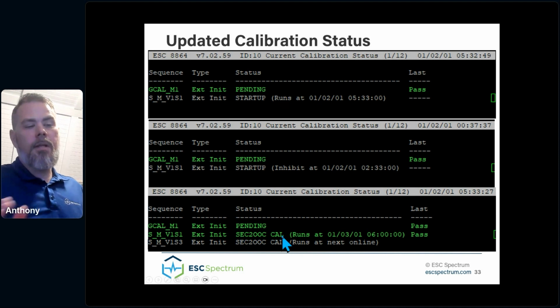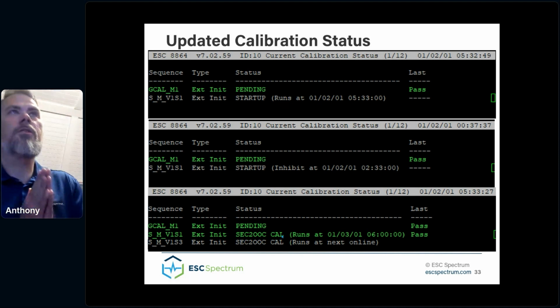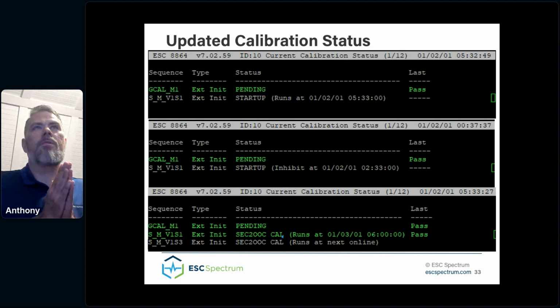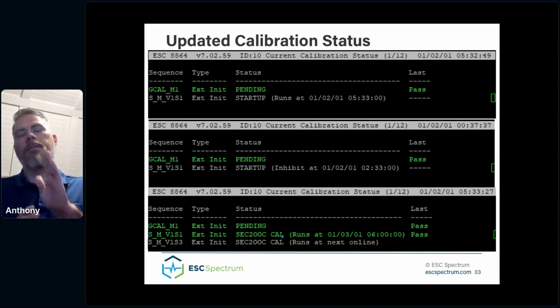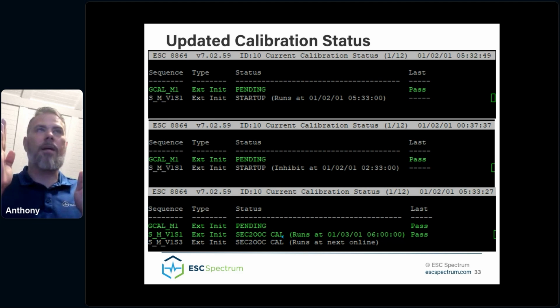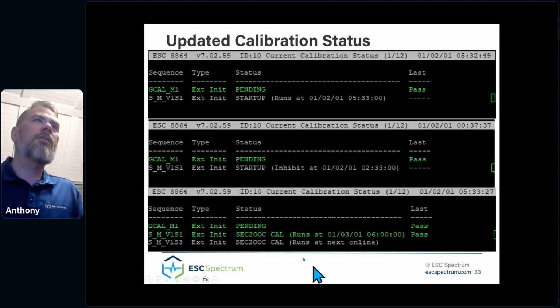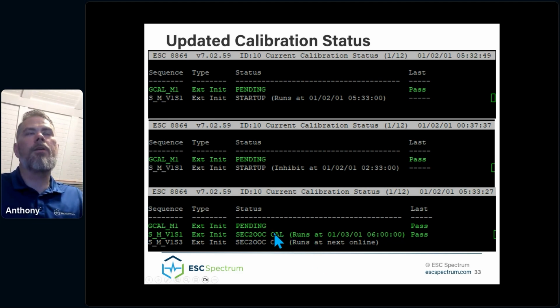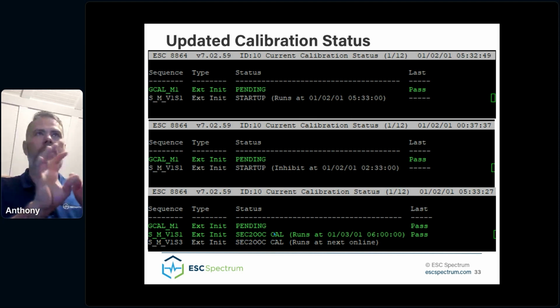If your sector OOC on a math channel configured in a calibration gets below the threshold, that sector OOC cal would be scheduled to run at a certain time. This is if you have not hit the threshold yet, but you know you're going to hit it at a certain time. This is when you would hit that. And this actually becomes the default status. When I showed on that previous slide that the sector OOC counter had reset, instead of a calibration just saying pending, it would now say sector OOC cal runs at this time.